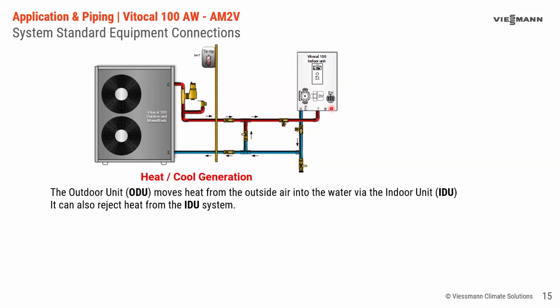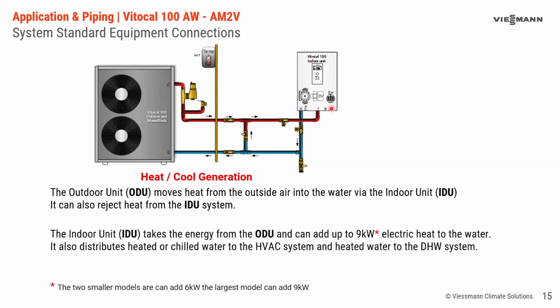So this is basically where the energy comes from. It's either moving it from the outdoor air, putting it to the outdoor air, or we're adding the electric heat, and this is what this portion of the machine is for. So this part of it we could call the heat or the cool generation. Now we're going to attach that, like I said, with the electric heat, and we can do up to 9 kilowatts of electric heat, and in the smaller ones, the 2 units are 6 kilowatts.